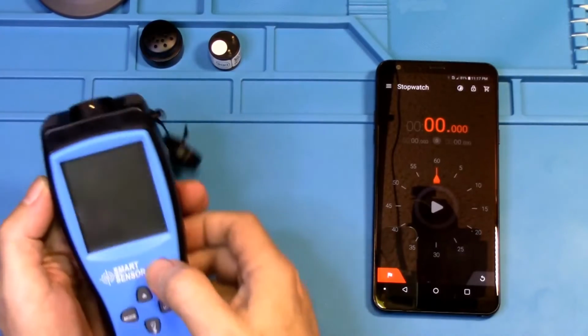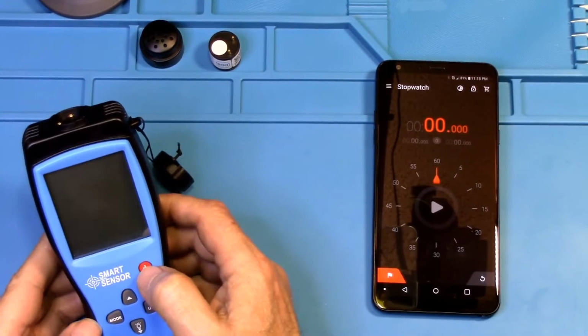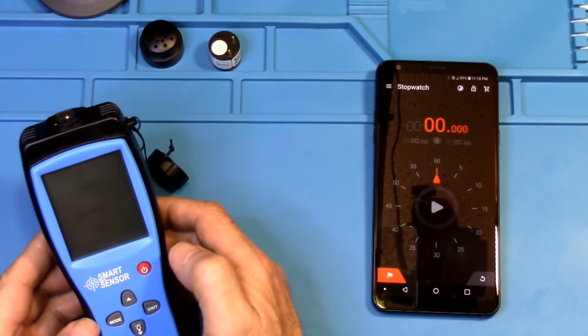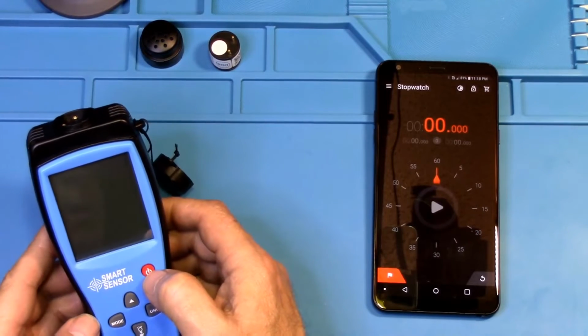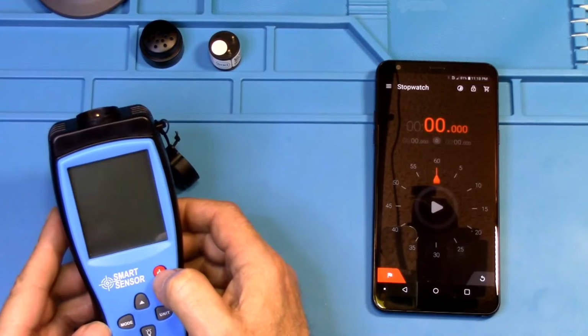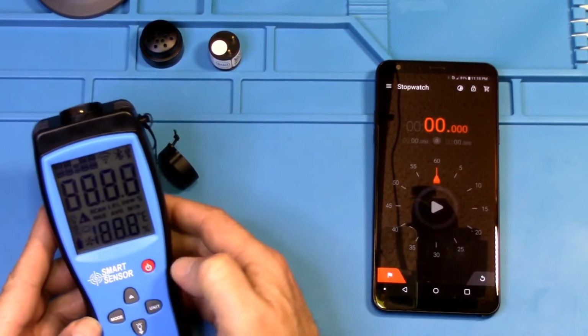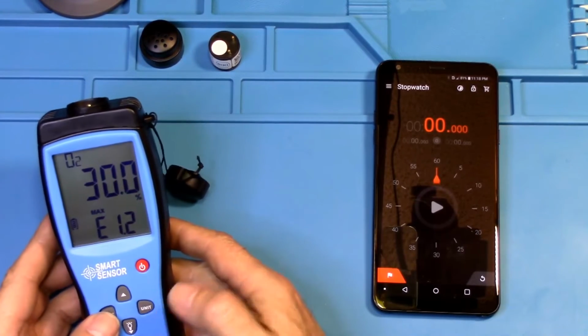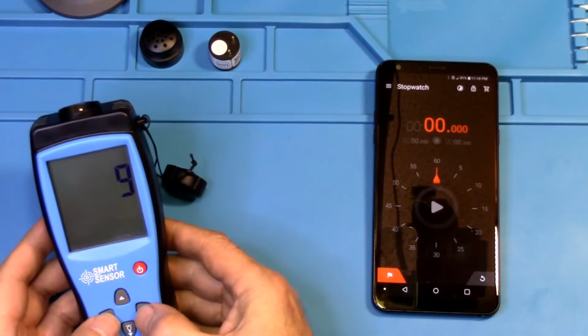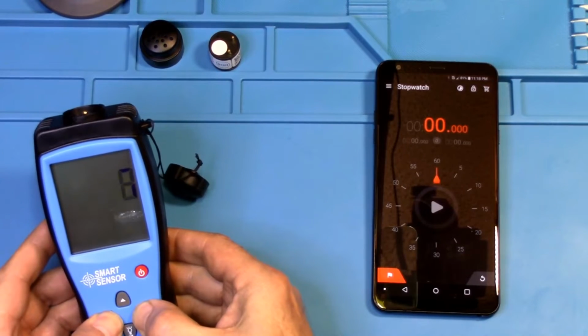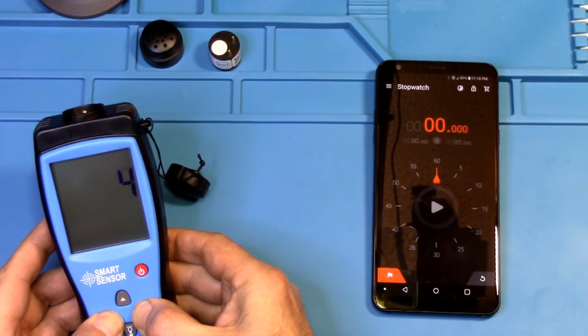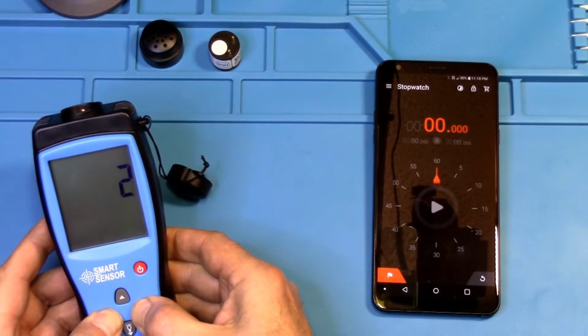Okay, now we're going to power this on. Step 1, remove the sensor from the meter. Now, step 2 is to turn the meter on. Okay, now during the countdown process, hold the mode button and the unit button together at the same time, and just hold it until the screen shows calibration.